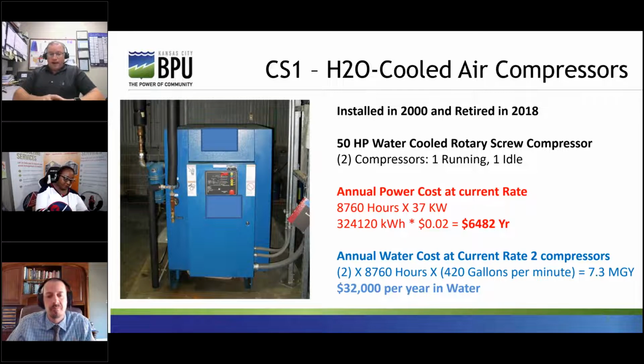Here's the kicker. For 18 years, these 2 were in service. They used 132,937,200 gallons of water for cooling, which could otherwise have been sold to our customers for around $576,000. That's a pretty significant operating cost. Energy use for the compressors was around 6,482 annually, since only one was in service at a time and the other was on standby. The babies were reliable for 18 years.